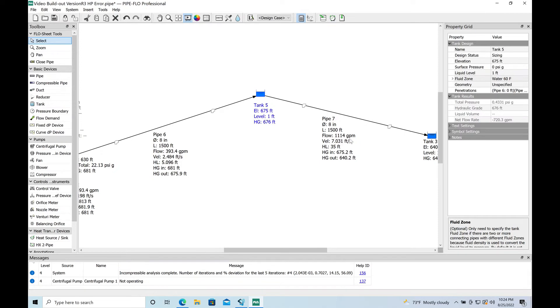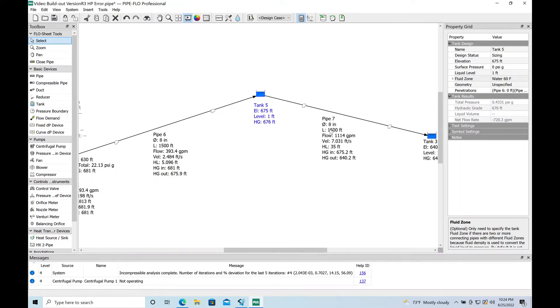We're kind of getting sort of an erroneous result here. We cannot pump more flow into this tank than what we're delivering from here, but it's because these tanks are sort of infinite water surfaces until you define them. Basically it's unable to deliver this much flow, but we do know that what's going to happen here is it's going to pump to this high point and it's going to drain by gravity through this system.